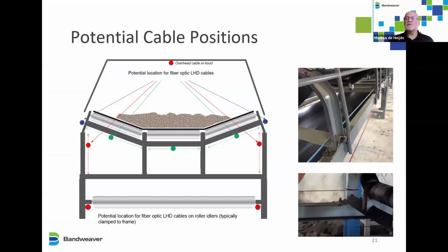Next, we're going to look at potential cable positions on the conveyor belt. The main thing to remember is that you want to be as close to the bearings as possible, so you can detect the temperature change quickly and deal with it efficiently. Every frame that I've seen in the field is different, so cable positions will be different as well. If you're close to the bearing and, for example, you get a rate of rise alarm, you can still prevent a fire. The overhead cable in the hood, if there is a hood, typically detects a fire when there's flammable material, so that will be more of a fire detection position.